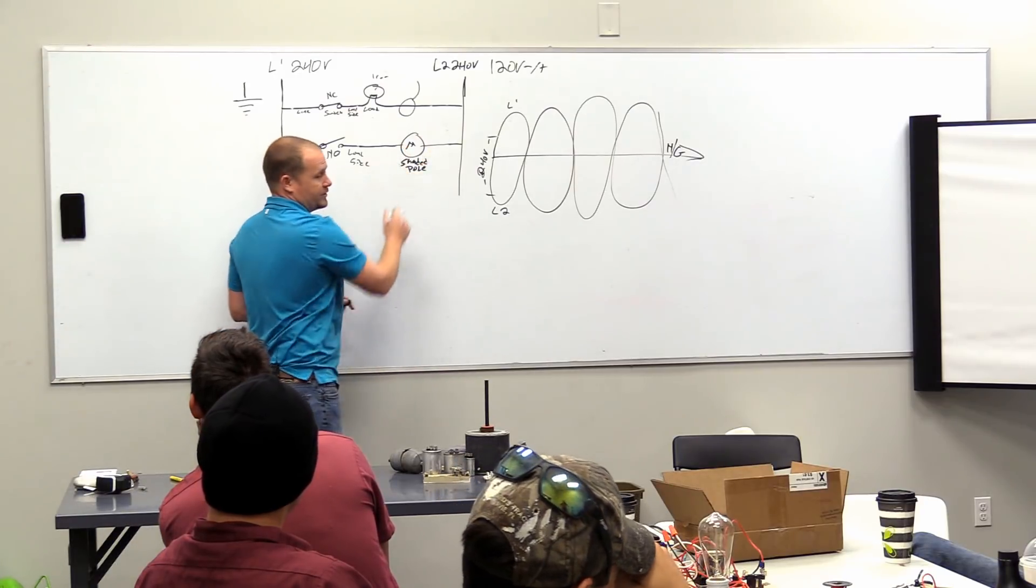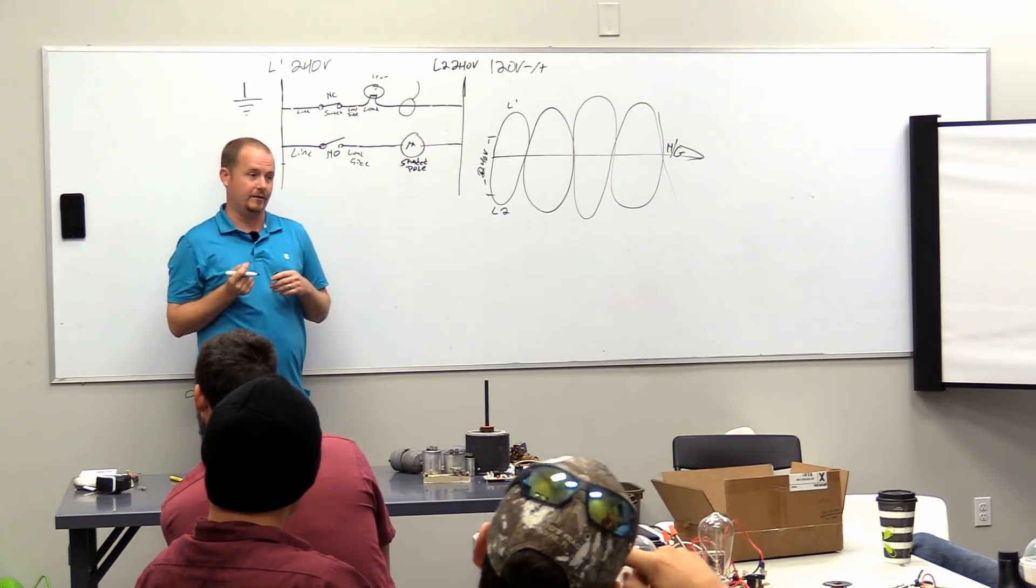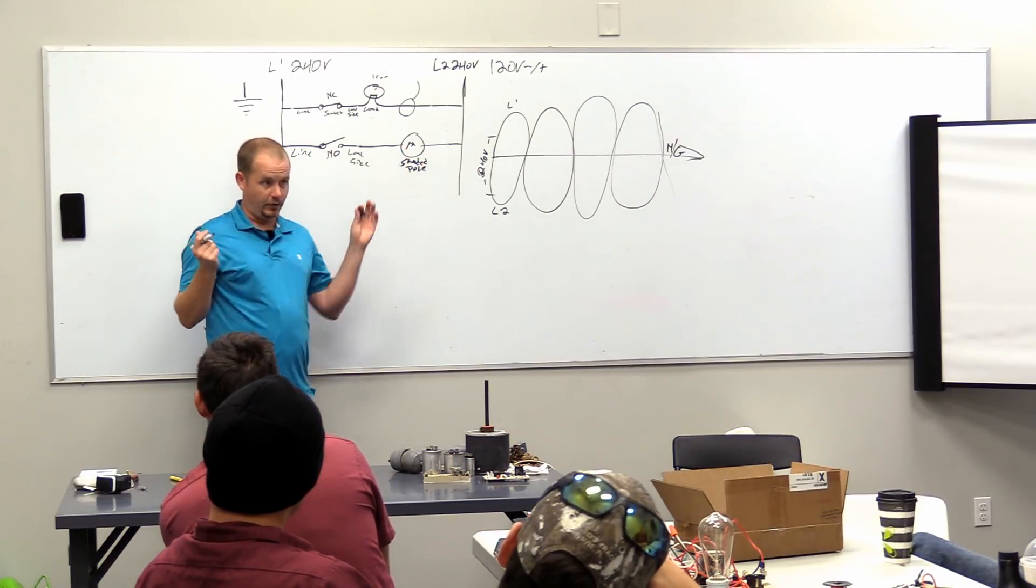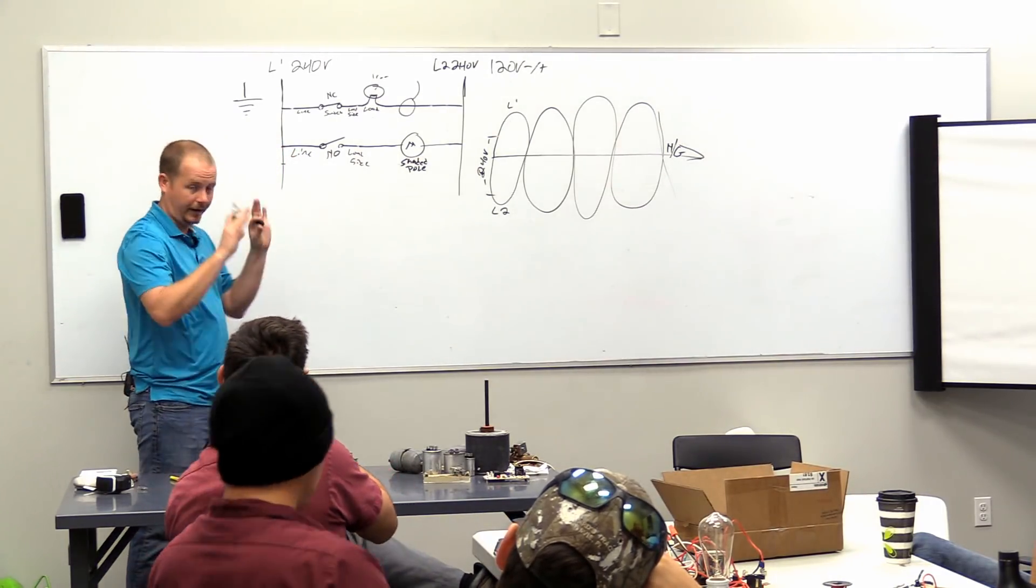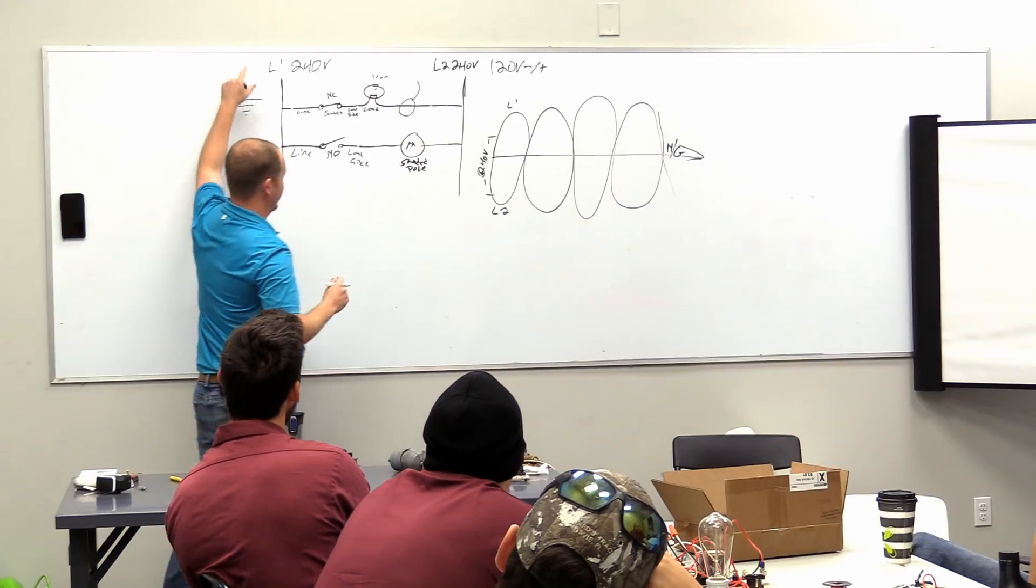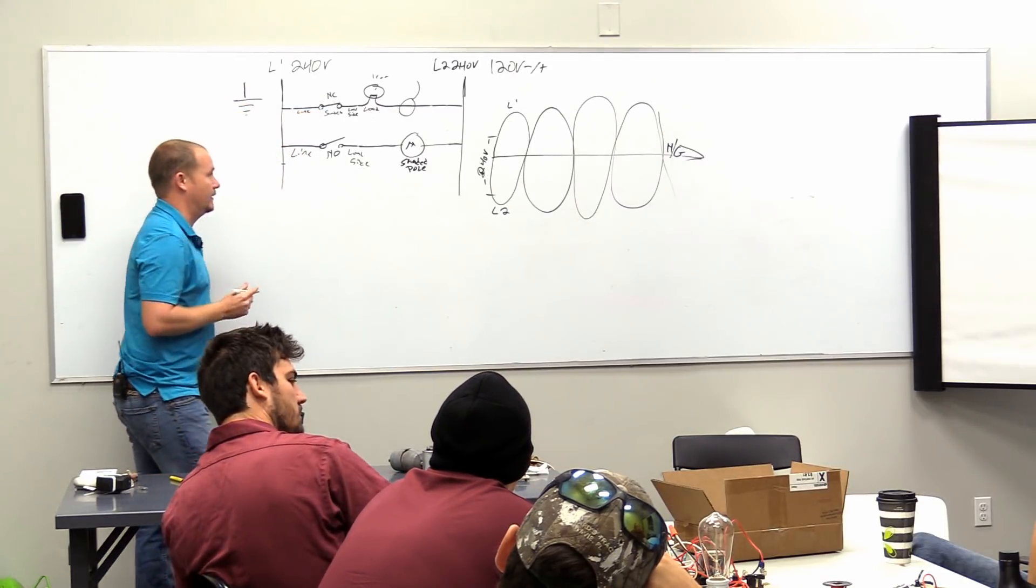All right. So we've got a shaded pole motor here. We know it's shaded pole because it only has two legs coming into it, right? Otherwise it would have to have a capacitor if it was a permanent split capacitor type motor. All right. So we've got 240 volts. We've got ground here.